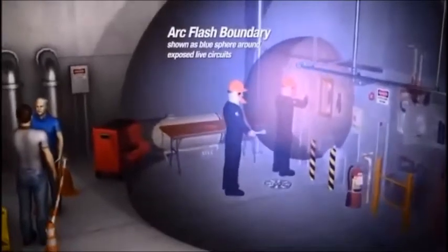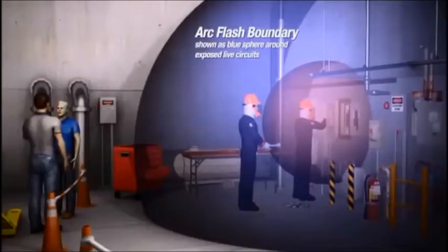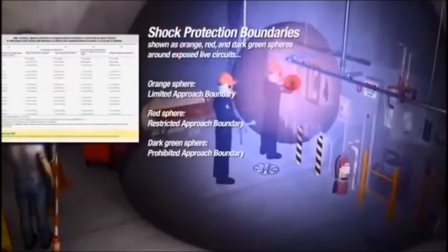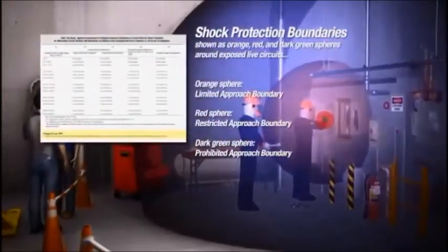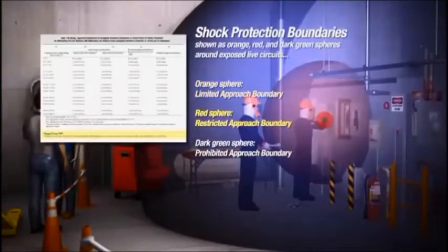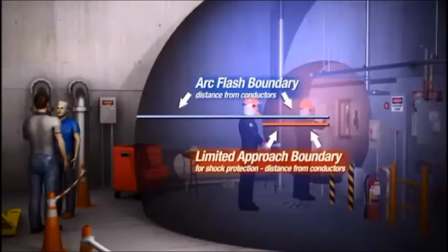The arc flash boundary is the approach limit at a specific distance from exposed live parts within which a person could receive a second degree burn. As seen in Table 130.4C and the illustrations, there are specified boundaries for limited, restricted, and prohibited approach. The arc flash boundary might be a greater distance from the energized electrical conductors or circuit parts than the limited approach boundary for shock protection.